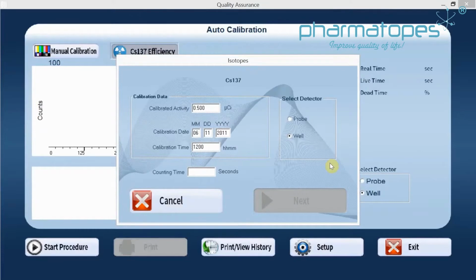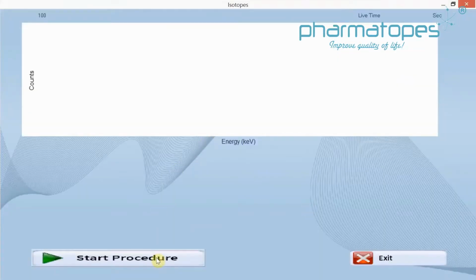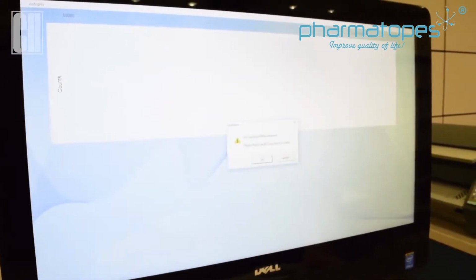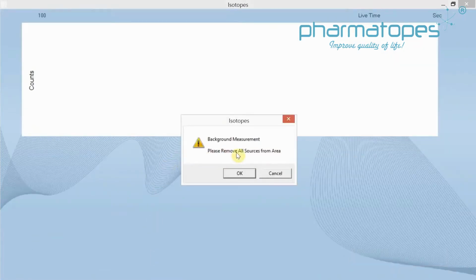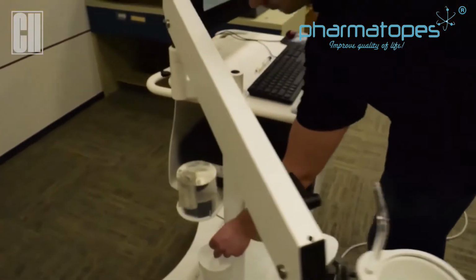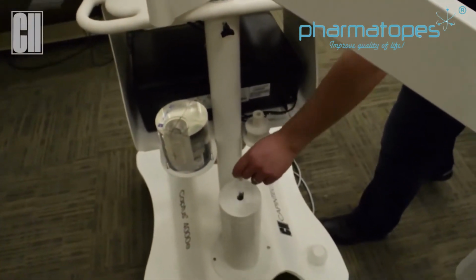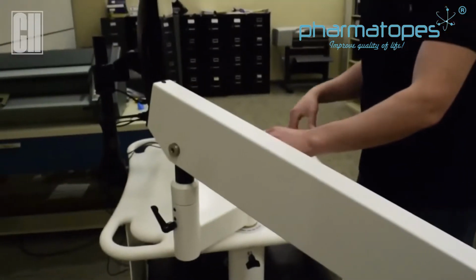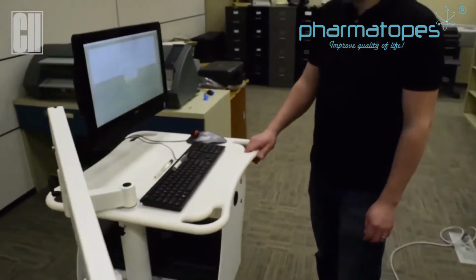In this case, we're going to click on well, and we're going to do a counting time and enter 60 seconds. Once we have that time in there, we're going to go to next, and then we're going to go to start procedure. Once we click on start procedure, it's going to tell us for the background, please remove all sources from the area. So we're going to remove our test source, and now we can click on OK.